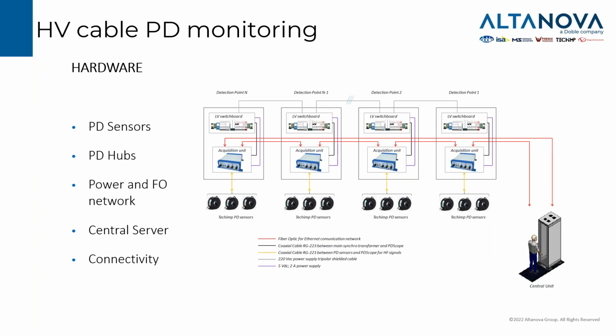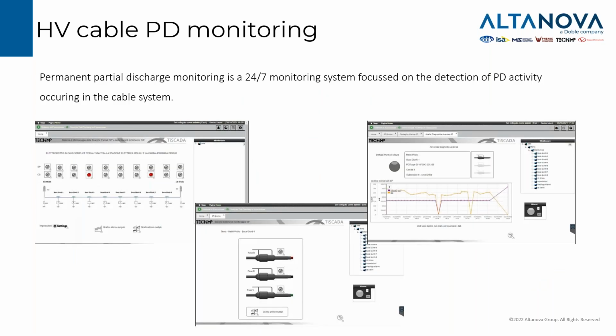This is, for example, the PD monitoring hardware required. For each link box and for each termination, we will have sensors connected to an acquisition unit. All these acquisition units are connected to each other and to a central unit with a fiber optic, and all of them must be energized from a power line. All the signals are sent to the central server that will then analyze the data, provide the alarms, and connect to the customer communication systems.